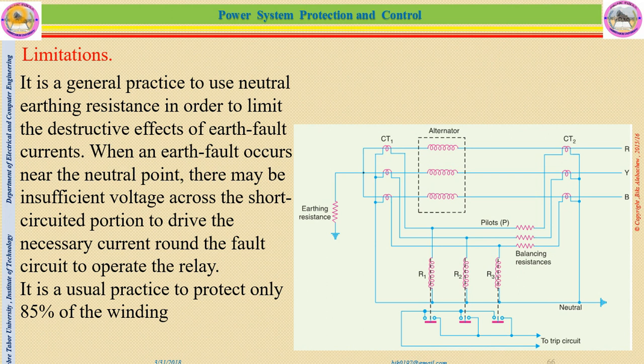It is a general practice to use neutral earthing resistance in order to limit the destructive effect of earth fault currents. When the earth fault occurs near the neutral point, there may be insufficient voltage across the short-circuited portion to drive the necessary current around the fault circuit to operate the relays. So when we are near the earth resistance or near the neutral point, there may not be sufficient induced voltage. At that time, the relay cannot get sufficient voltage to operate, and it is usual practice to protect only 80% of the winding by using this differential protection system.